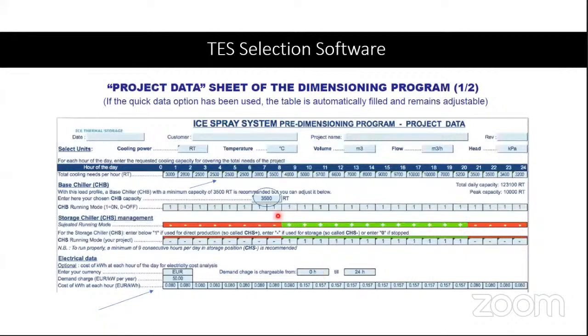This is how the software looks. You see the load profile is entered. The entire 24-hour load profile is entered here. There is also a calculation of the peak capacity here. It has been picked. You could also enter, although it is fixed by default, your base load chiller capacity, that is, out of the total load, this much should be the base load chiller capacity.